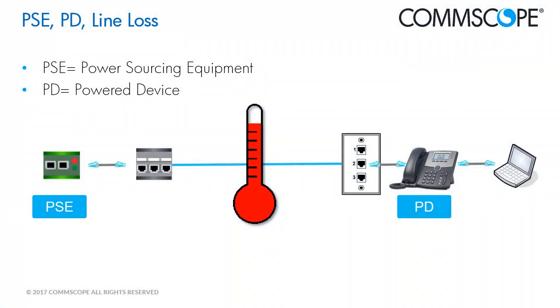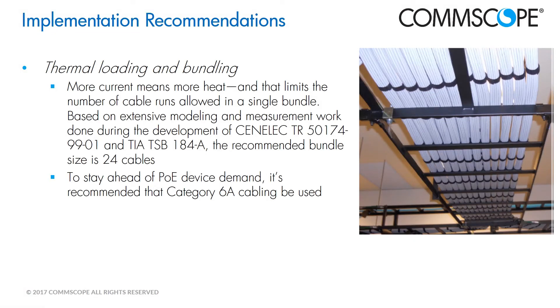Why is cable bundle size important now? PoE offers incredible potential but also comes with its own limits and restrictions that can impact how a network is designed and deployed. As newer PoE standards allow higher power levels over UTP cabling, and as more and more PoE devices start using this capability, the line loss, heat dissipation, and number of powered cables in a bundle are factors that take more relevance. TIA has determined that a bundle of 24 cables should be the maximum recommended. CommScope recommends Category 6A cable to stay ahead of PoE demand.